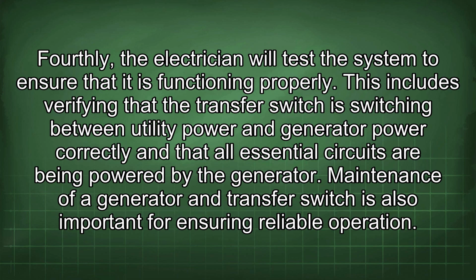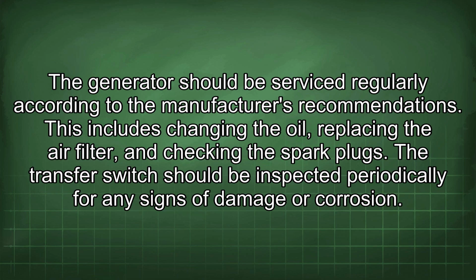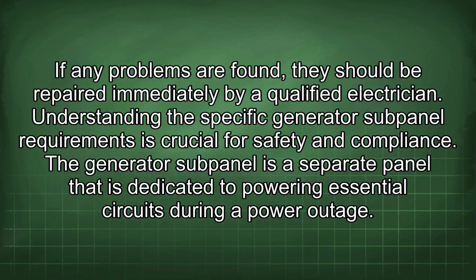Maintenance of a generator and transfer switch is also important for ensuring reliable operation. The generator should be serviced regularly according to the manufacturer's recommendations. This includes changing the oil, replacing the air filter, and checking the spark plugs. The transfer switch should be inspected periodically for any signs of damage or corrosion. If any problems are found, they should be repaired immediately by a qualified electrician.